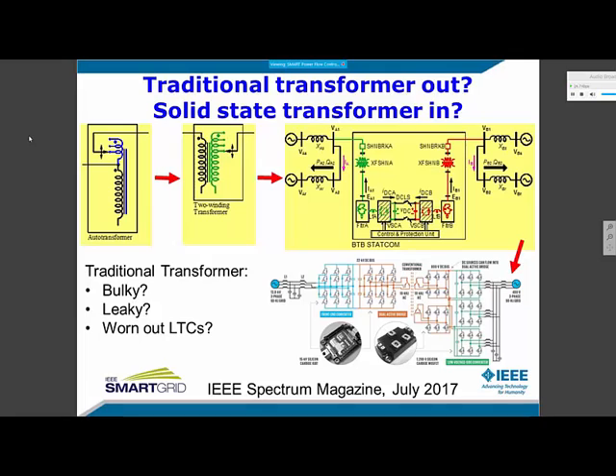Now, this was described in last month's IEEE Spectrum magazine, and the author's claim is that the traditional transformer is bulky, oil may leak, and the LTC will be worn out. So we should take the old traditional transformer of the 19th century and favor this proposed new solid-state transformer. Please look at that article, and it has a lot of thought-provoking comments.